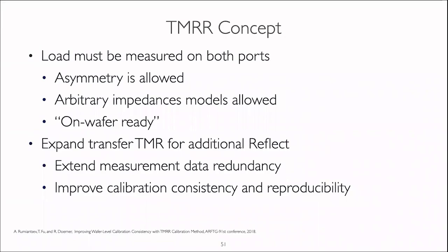Why are thru-match-reflect calibration algorithms more preferable for wafer-level measurements? First of all, they measure both load standards, the port 1 and port 2 loads, independently from each other, so the system is fully calibrated with the loads. And asymmetry of the load is allowed.